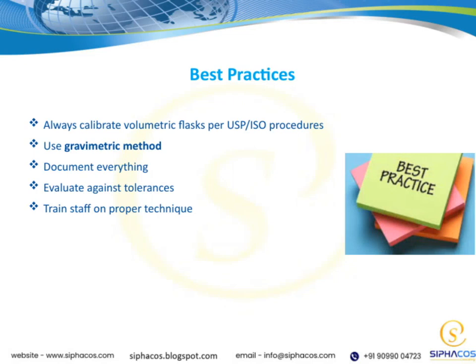Let's talk about some best practices to ensure accuracy and consistency in our procedures. First, always calibrate volumetric flasks according to USP or ISO procedures. This step is crucial because it guarantees that our measurements are reliable and traceable to recognized standards. Next, I recommend using the gravimetric method whenever possible. It tends to be more precise and helps verify the accuracy of our measurements. Documentation is another key point. Make sure you record every step and detail thoroughly. Accurate documentation supports traceability and helps in audits or troubleshooting. When evaluating your results, always compare them against specified tolerances to confirm they meet quality standards. Lastly, training staff on proper technique cannot be overstated. Well-trained personnel are essential for maintaining consistency and reducing errors.